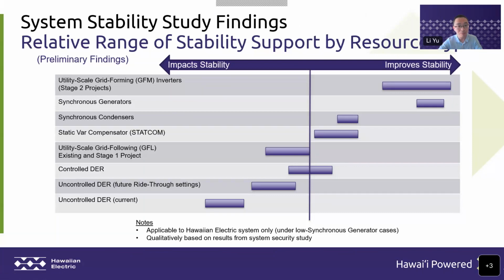And I believe if there are new technologies such as StatCom plus supercap, the so-called GFM StatCom, or even an existing synchronous condenser plus flywheel or plus battery, definitely they can do much better for improved system stability. For the DER, if we can enable the control so it can be curtailed during a certain time frame for system operation needs, we believe their impact on system stability can be improved.